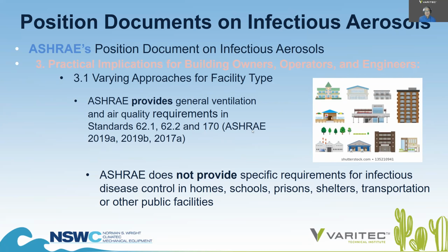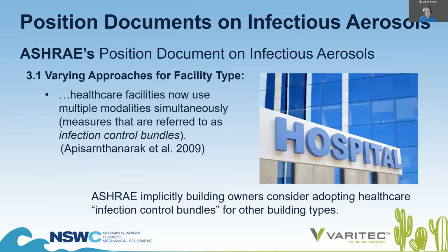So what we have to lean on with regard to commercial buildings is applying appropriately ASHRAE standard 62.1 for the required ventilation air to get to the breathing zone of the occupants. The varying approaches advocated by ASHRAE for facility types, though, goes on to recognize their statements on healthcare facilities and how they use what they call multiple modalities simultaneously to create what are called infection control bundles. And from ASHRAE's incorporation of this language into the position document, I believe what ASHRAE is saying, that building owners consider adopting healthcare infection control bundles for other types of buildings.